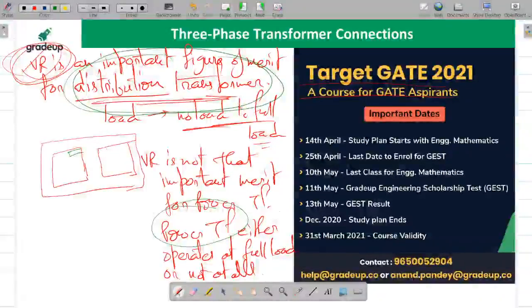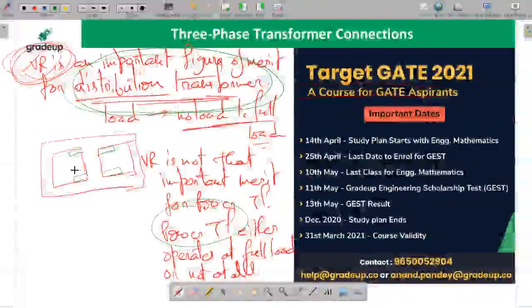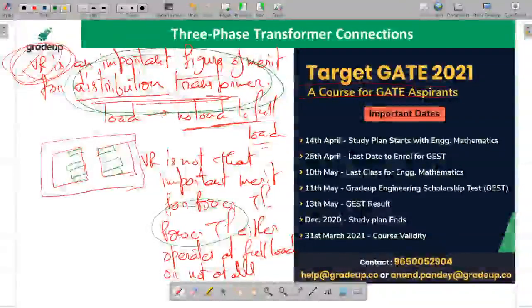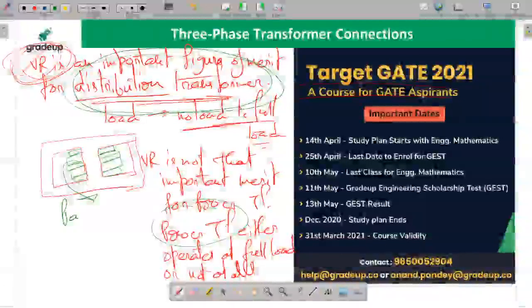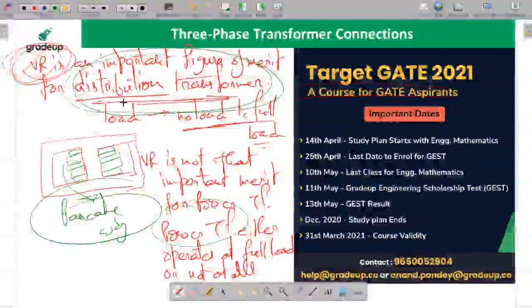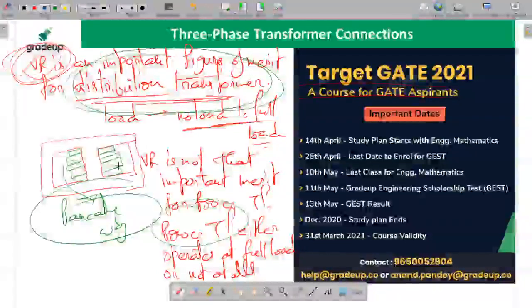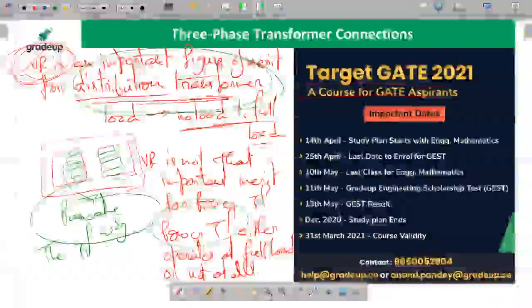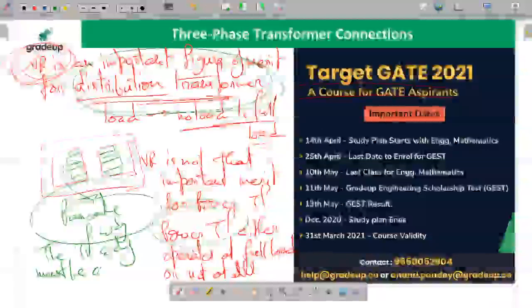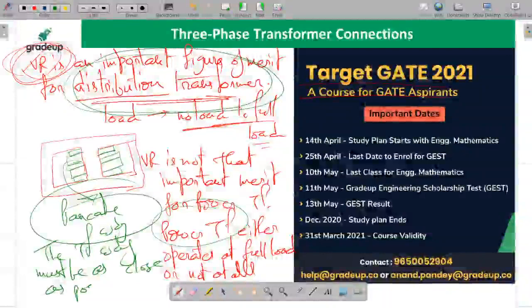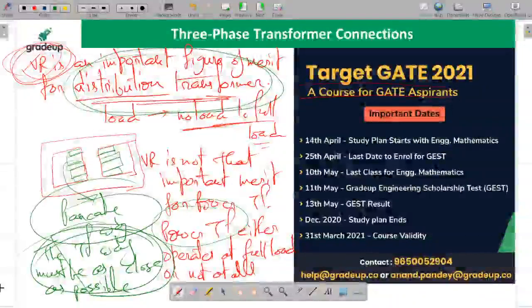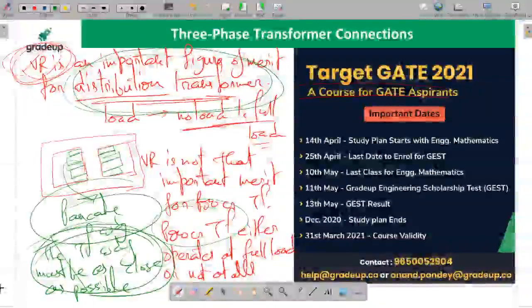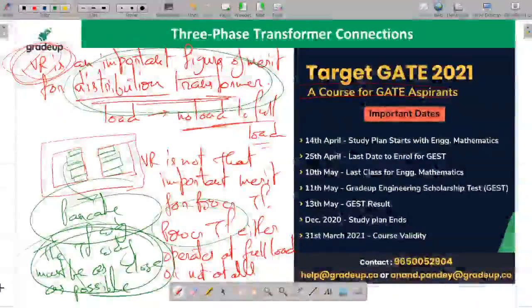So this is LV winding, this is HV winding, then again LV winding, then again HV winding, like this. It is also called pancake winding. The basic idea to improve the voltage regulation and reduce the leakage flux is that the transformer windings must be as close as possible. The two windings of the transformer, whether primary or secondary, must be as close as possible. I hope it is clear to all of you.